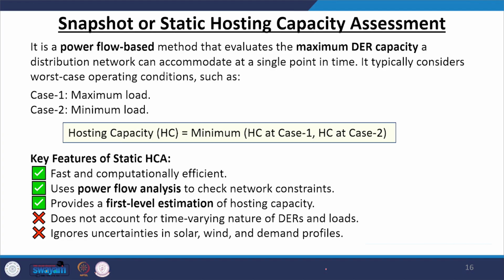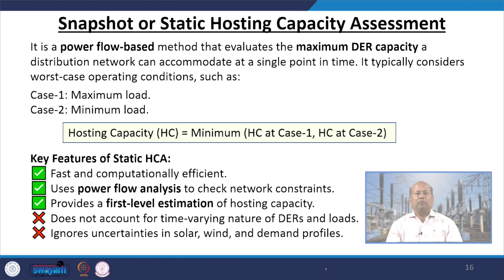Let us focus on snapshot or static hosting capacity assessment. It is a power flow based method that evaluates the maximum DER capacity a distribution network can accommodate at a single point in time. It typically considers a worst case operating condition, such as maximum load as case 1, as well as case 2, which is of minimum load. So the hosting capacity HC is the minimum of the hosting capacity of case 1 and the hosting capacity of case 2.